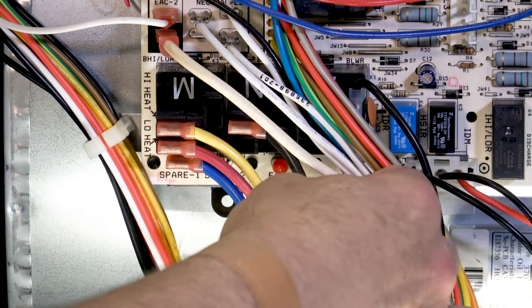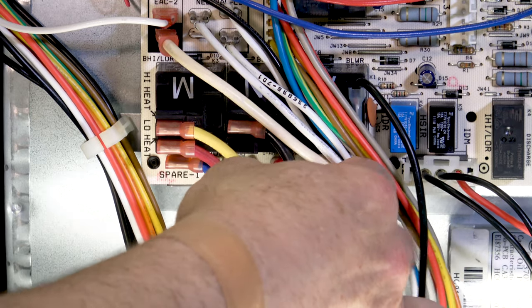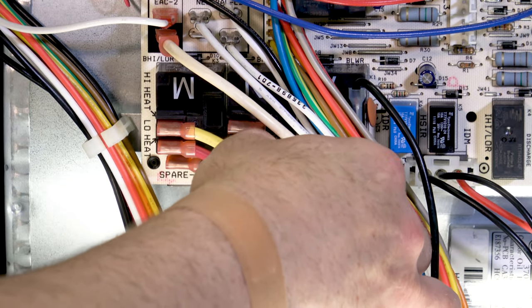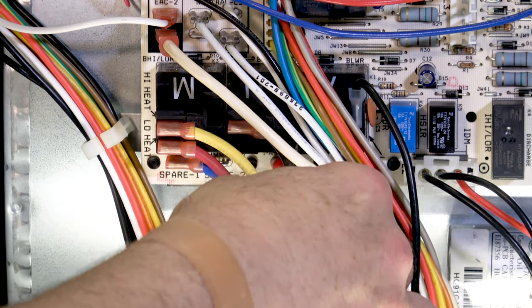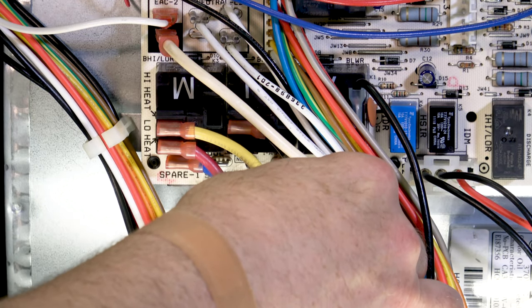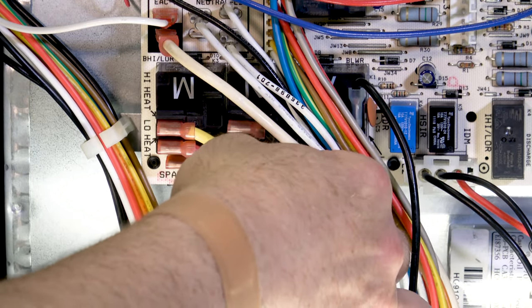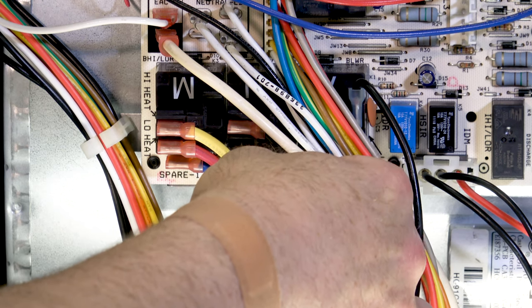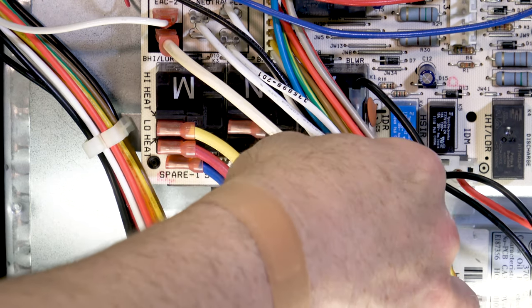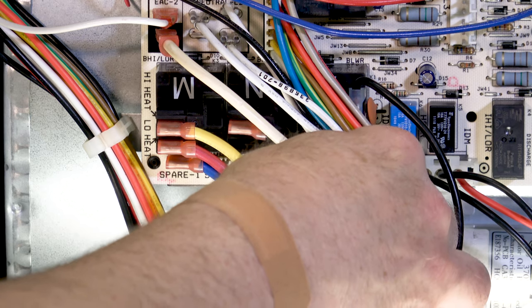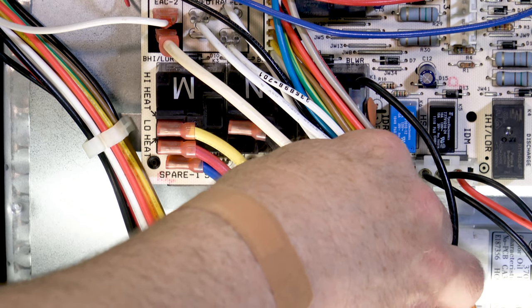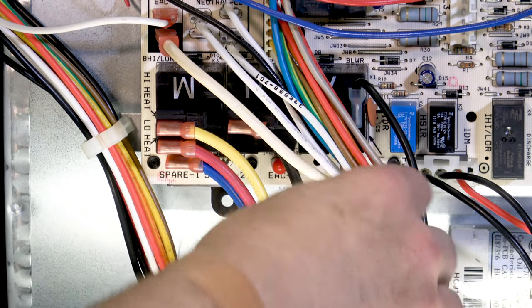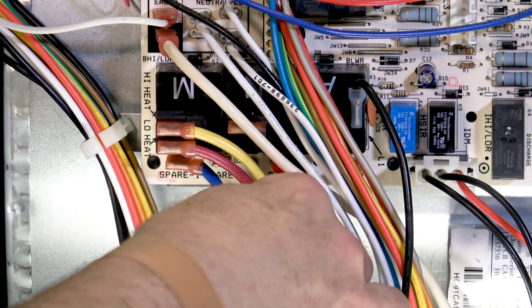On this motor, our black is our high, our yellow speed is our medium high, and red is our low. The low is attached to our low heat, the yellow which is medium high is attached to the high heat, and our high speed black is on our cooling speed for our highest CFM output.